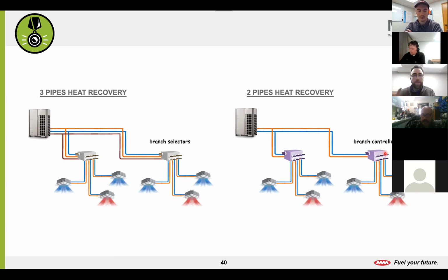So it's same components, same technology. It's just instead of having it all done at the outdoor unit, we're moving some of it to our indoor unit. Main benefit of that is going to be cost for installation, really. It's one less pipe we have to run. So on a 3-pipe system, we're looking at 3 pipes we've got to send to our branch controllers. On a 2-pipe system, obviously we're only sending 2 pipes through. It can squeeze through tighter areas, with less material costs for install. The trade-off is usually our branch controllers are a little bit bigger. So that's something that we have to explore. We've got to make sure that wherever we're putting them, say a drop ceiling, a space, a hallway, a closet, something like that, it's got to be big enough to allow for that increased size there.